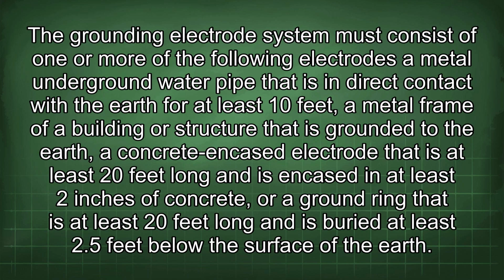The grounding electrode system must consist of one or more of the following electrodes: a metal underground water pipe that is in direct contact with the earth for at least 10 feet, a metal frame of a building or structure that is grounded to the earth, a concrete encased electrode that is at least 20 feet long and is encased in at least 2 inches of concrete, or a ground ring that is at least 20 feet long and is buried at least 2.5 feet below the surface of the earth.